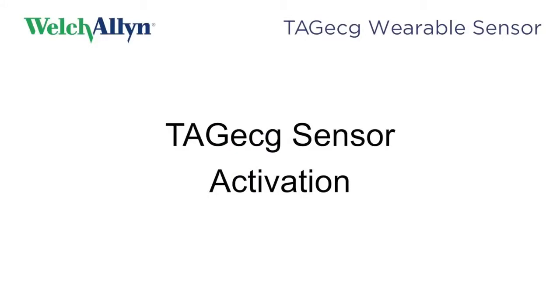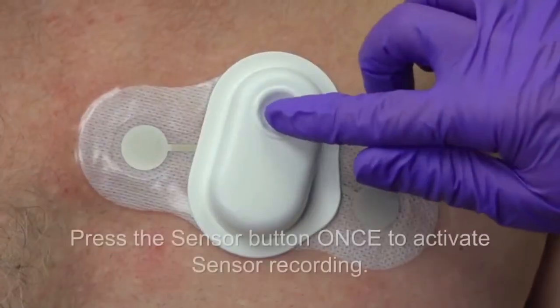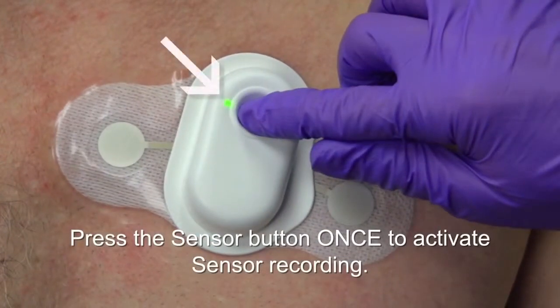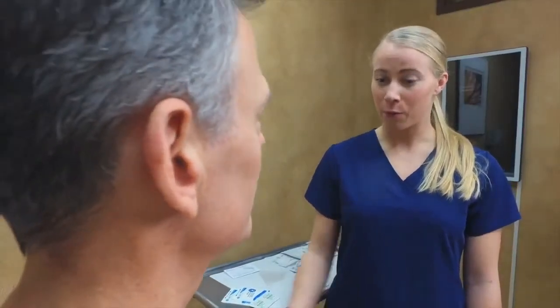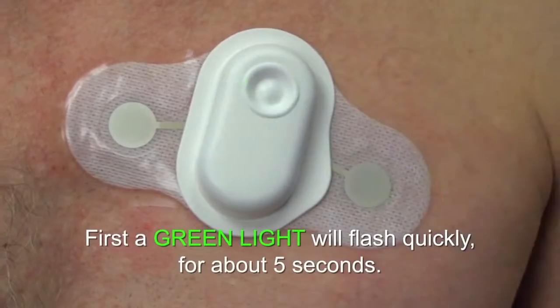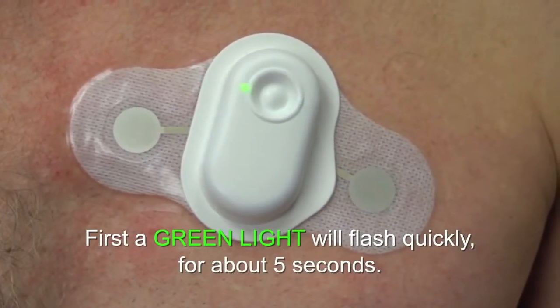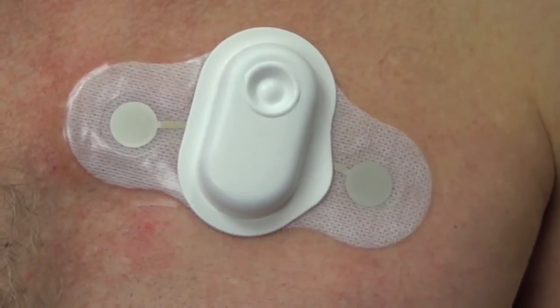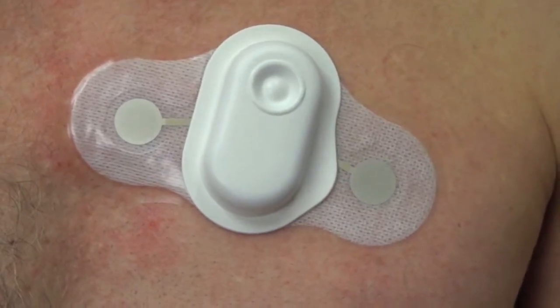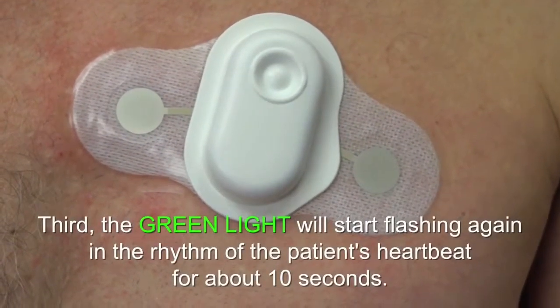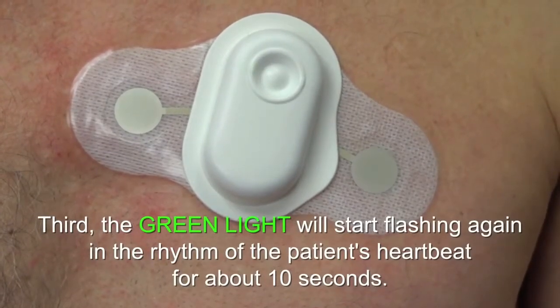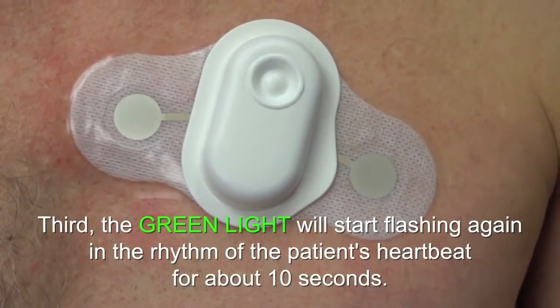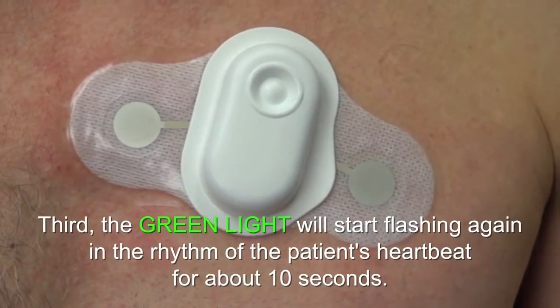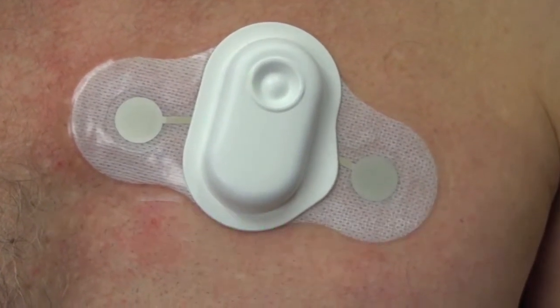TAGecg sensor activation. Ask the patient to remain still and press the sensor button once to activate sensor recording. If the TAGecg sensor has been activated successfully, you will see the following. First, a green light will flash quickly for about 5 seconds. Second, this green light will turn off for another 5 seconds. Third, the green light will start flashing again in the same rhythm as the patient's heartbeat for about 10 seconds. Fourth, the green light will then turn off completely.